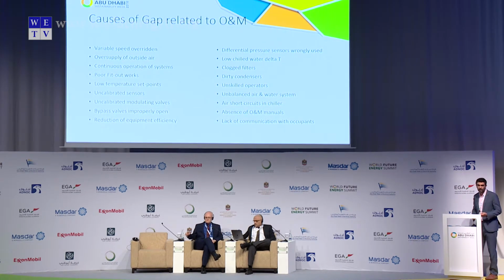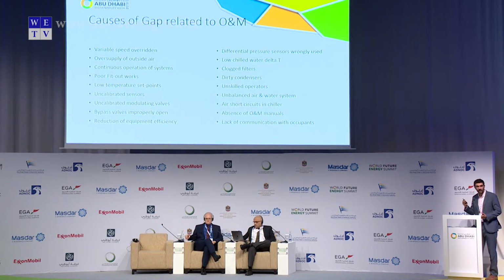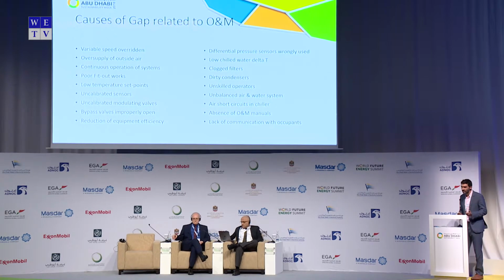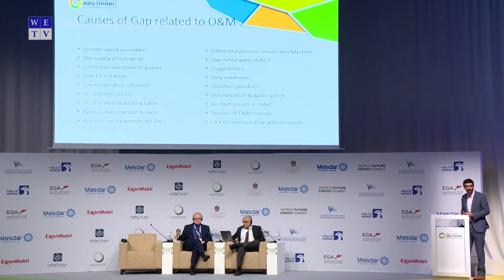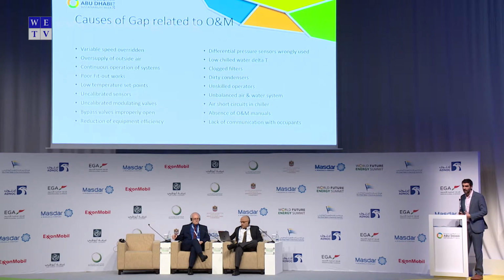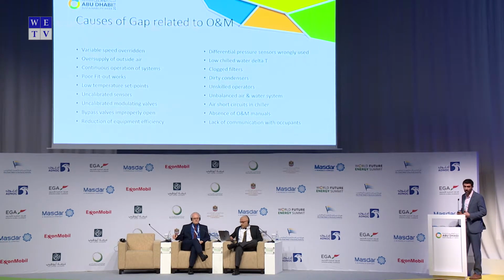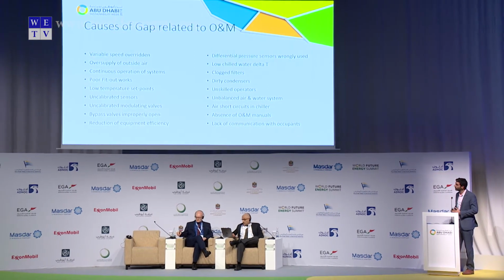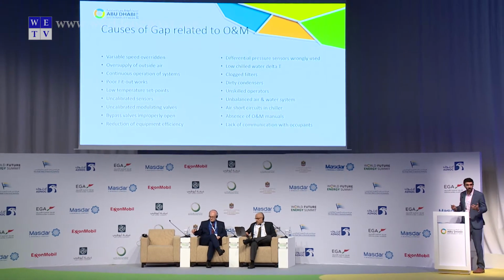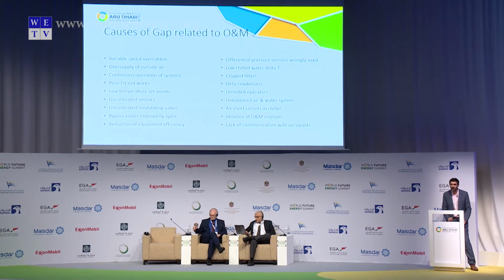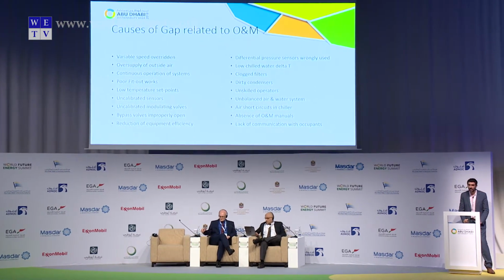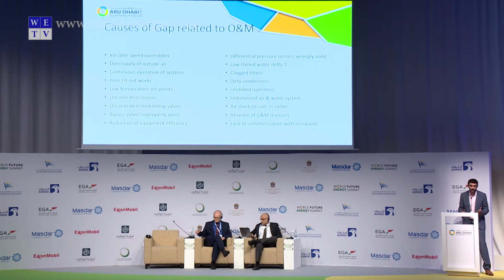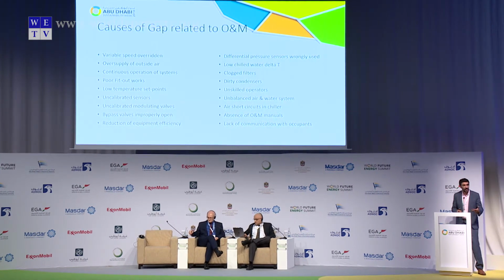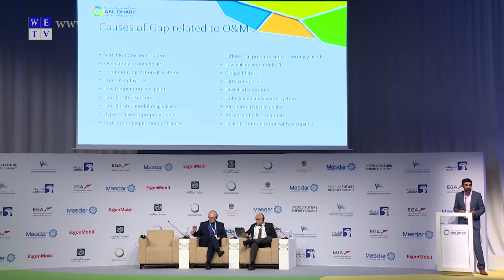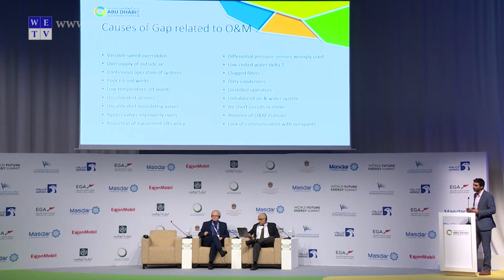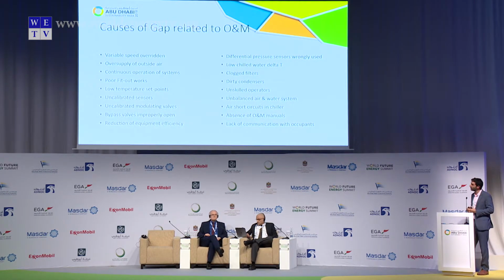So operators may override them, probably because somebody on a higher floor of the building is feeling hot. So as a simple remedy, they would just ramp up the fans or the pumps, and therefore consume much more energy than what the design wanted to be consumed. Oversupply of outside air: probably someone called the operator and said, there is a smell in my office, could you please help me? And the operator could, as an easy solution again, ramp up the fan speed of the outside air, and therefore consume much more energy on the outside air handling unit.